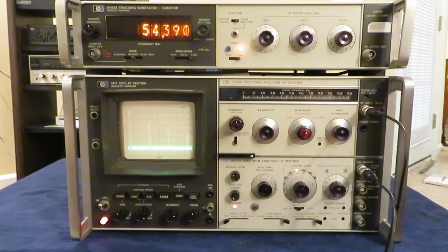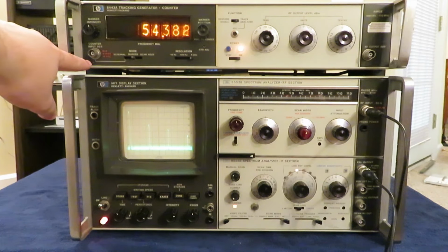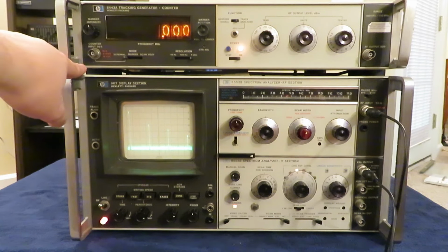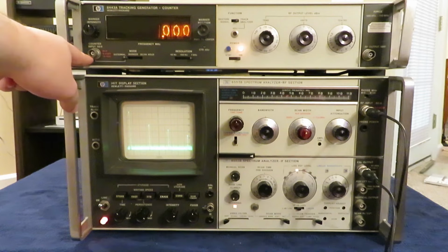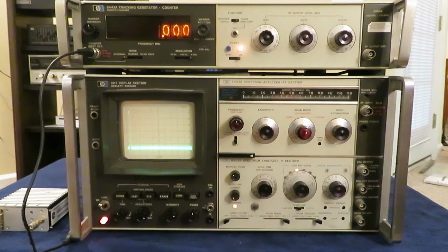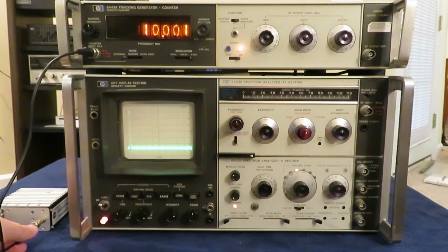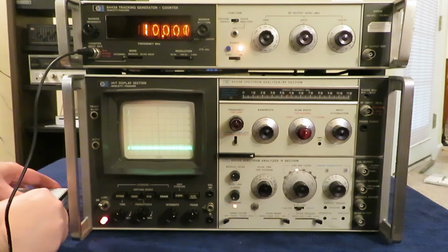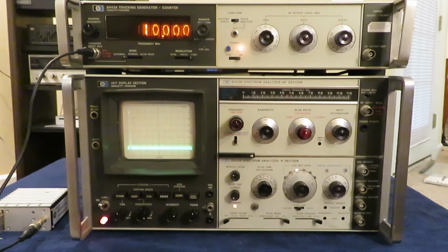The frequency counter also has the ability to be used as an external frequency counter through this input here. You slide that over to external mode and it will just read the frequency through this input here. So what I've brought into frame on the left over there is a 10 megahertz rubidium reference. I'll bring this up later when we talk about calibrating the internal reference oscillator in this thing. But for now, we can just use it to demonstrate the external counter functionality of it, where you can see if I plug it in here, it shows 10 megahertz on the counter.